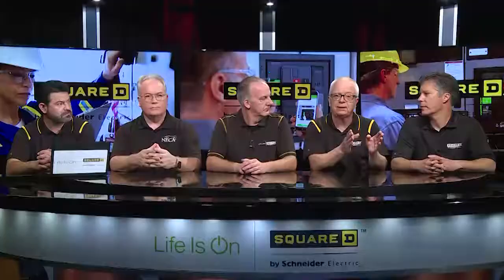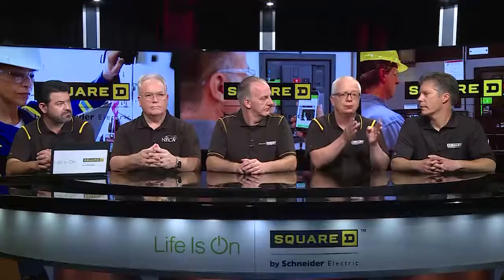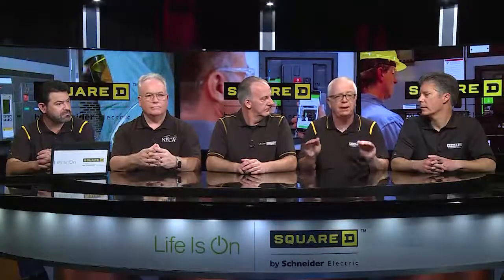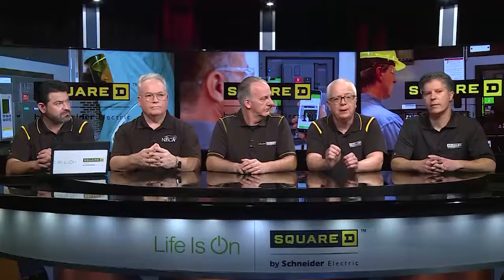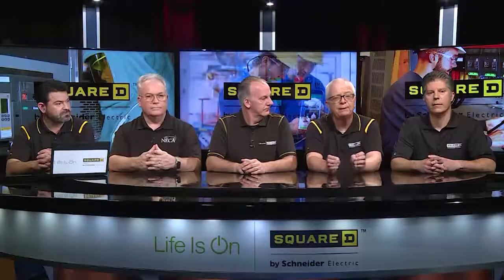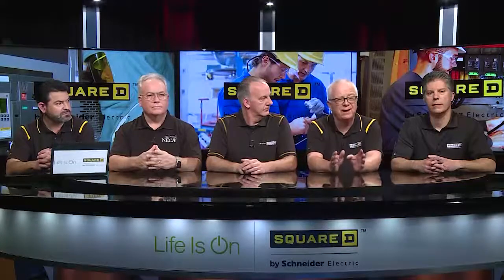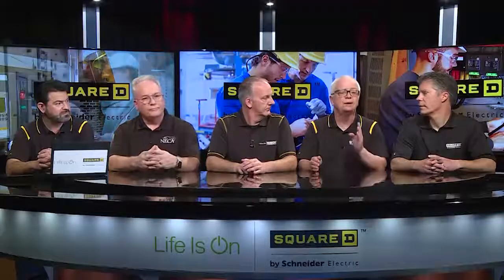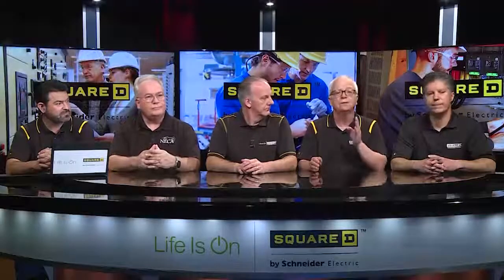Keep in mind that now all service equipment — without regard to what it is — is not limited, as Chad pointed out, to switchgear, switchboards, and panel boards. If it's service-supplied, it's going to have to have protection from inadvertent contact. This protection does not eliminate the possibility, but it significantly reduces the likelihood of an occurrence, and that's a big win for worker safety.